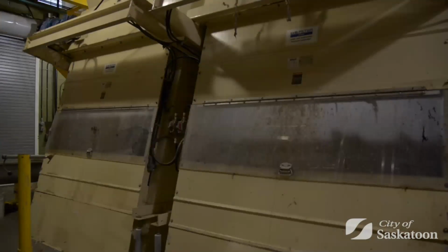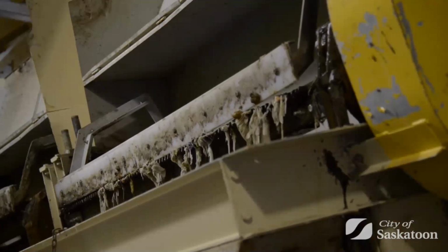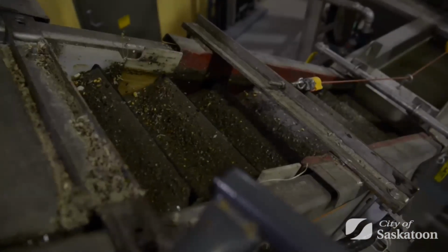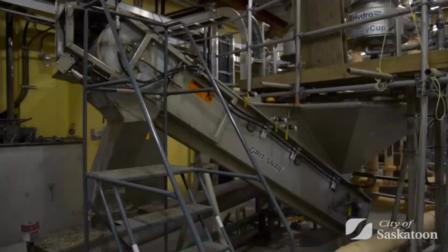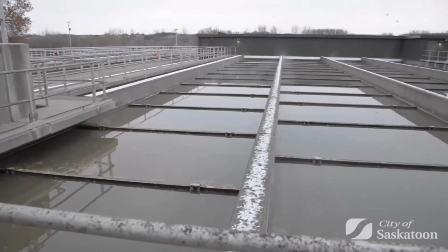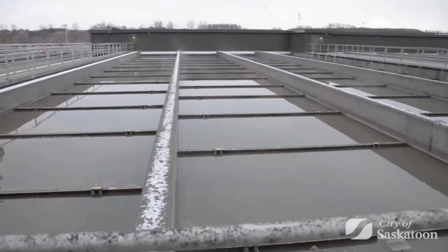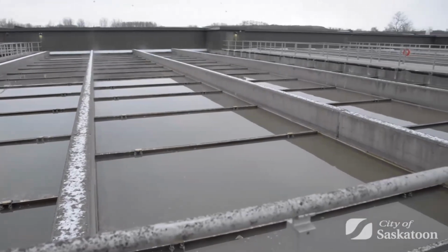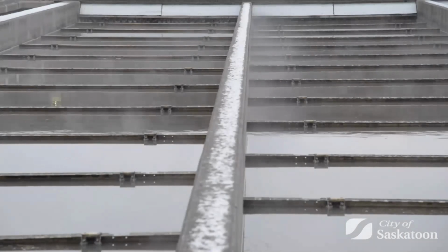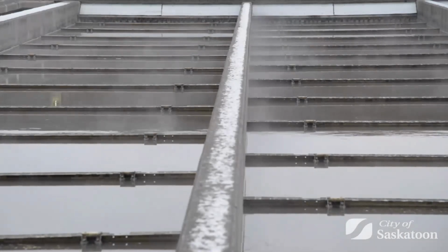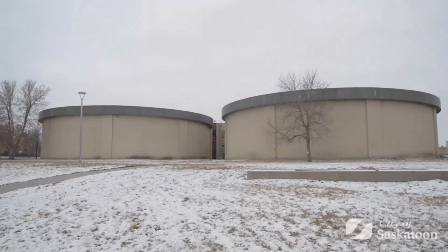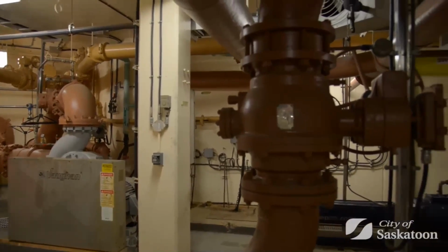In the first stage in this treatment process, the wastewater passes through a series of screens to remove materials larger than 12.5 millimeters. These materials are cleaned and transported to the landfill. The wastewater then travels to large basins where heavier materials, called sludge, settle and sink to the bottom. Lighter materials, including fats and oils, called scum, float to the top. The sludge and scum are sent to fermenters and digesters, where bacteria breaks it down further.